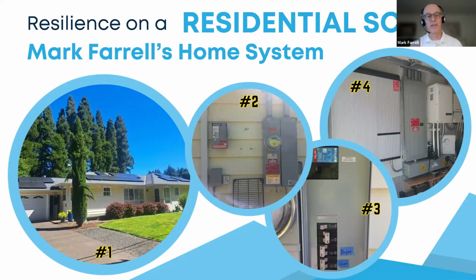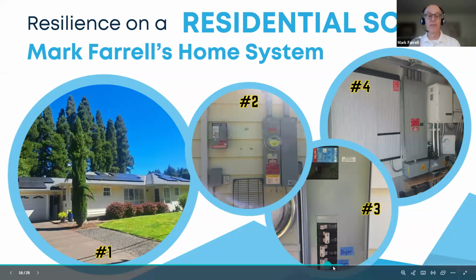Just on the right side is the service coming into the home with the meter, as you can see there, and in red are diagrams about the system, again a safety feature. That panel on the right of the meter is my unprotected loads panel. We'll take a look at that later. Actually, number three shows it right there. It's kind of hard to see, but those are circuits that I don't have protected. They're not backed up during an outage.